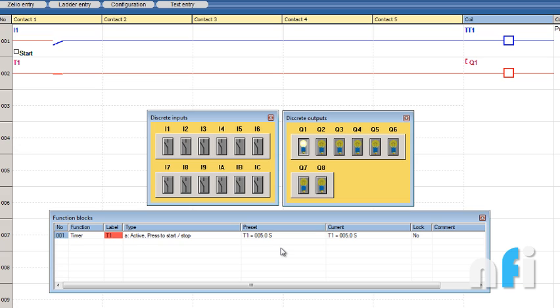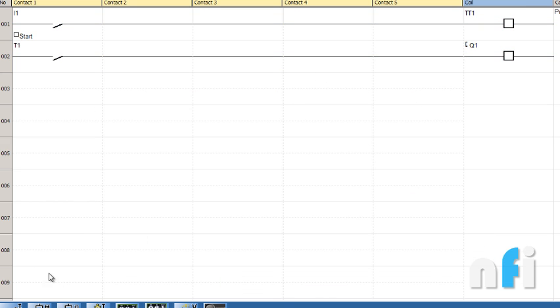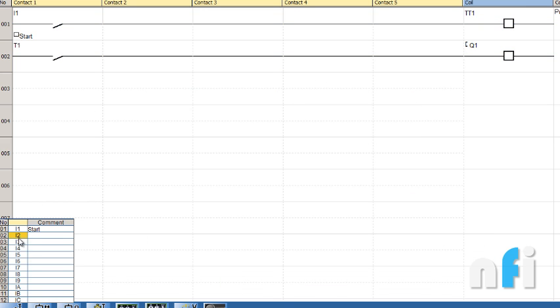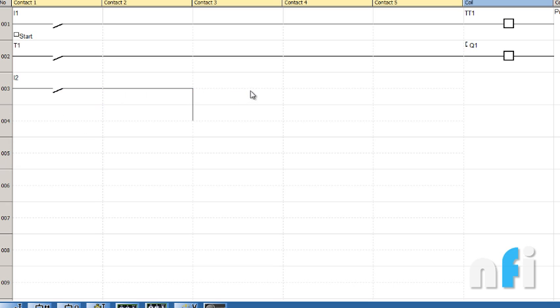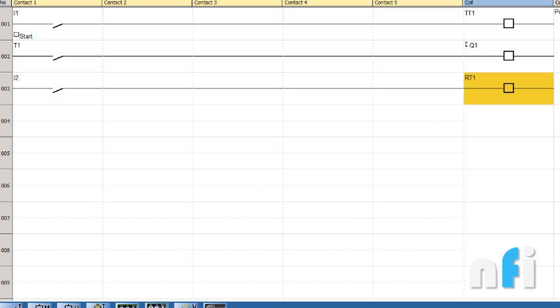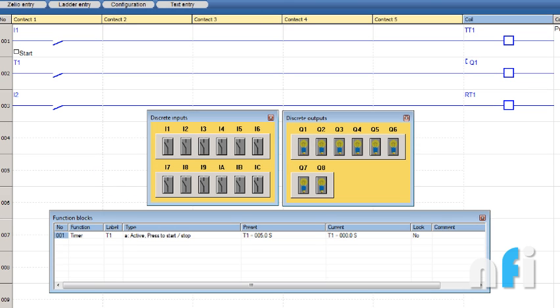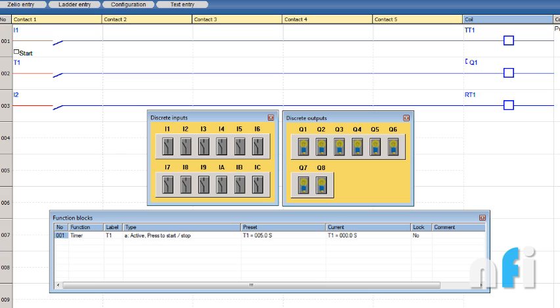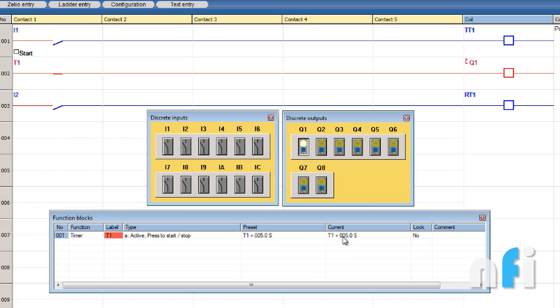Now the question is how to stop the output when there are no functions available here, no ladder logic to stop the output. For that we will reset the timer. I'll take another input I2, and here I'll take this reset function. This will reset the output and the accumulated time. Now you'll see - giving a pulse, timer has started, it's counting. The moment it reaches five, by using I2 it's going to reset T1. It will reset this current time. If this time is zero, these are unequal and the output will be off.